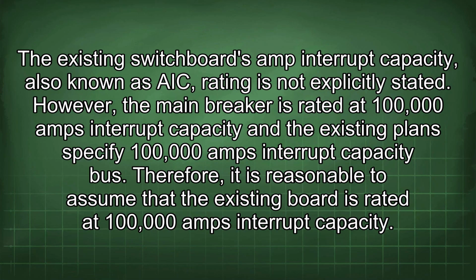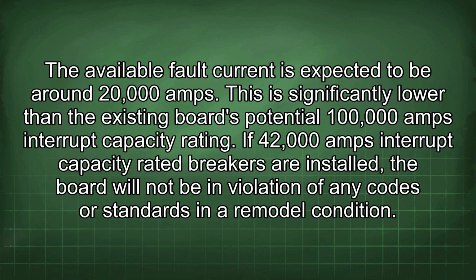The existing switchboard's amp interrupt capacity, also known as AIC, rating is not explicitly stated. However, the main breaker is rated at 100,000 amps interrupt capacity, and the existing plans specify a 100,000 amps interrupt capacity bus. Therefore, it is reasonable to assume that the existing board is rated at 100,000 amps interrupt capacity. The available fault current is expected to be around 20,000 amps. This is significantly lower than the existing board's potential 100,000 amps interrupt capacity rating.